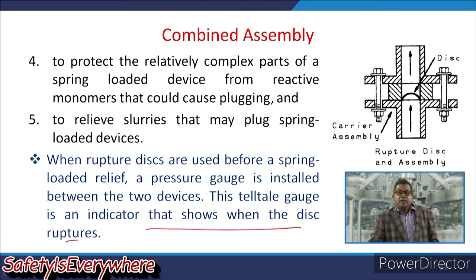So when rupture discs are used before a spring loaded relief device, a pressure gauge is usually installed between these two devices. The telltale gauge is an indicator that shows when the disc ruptures. So again there is a proper arrangement for indicating when this particular disc ruptures.